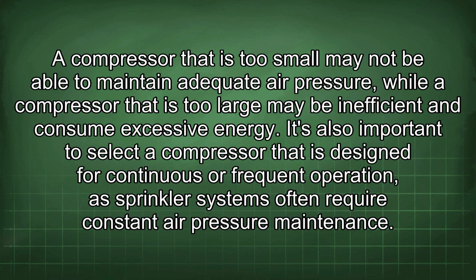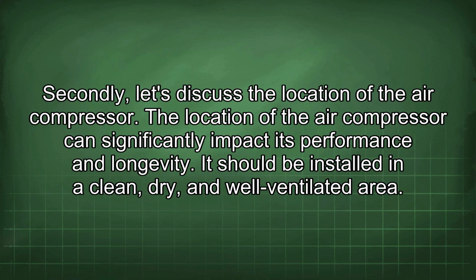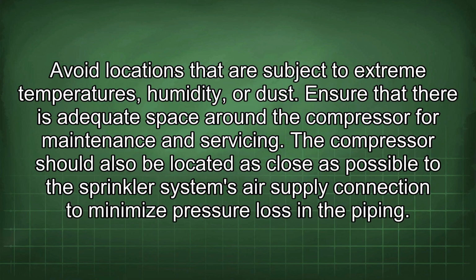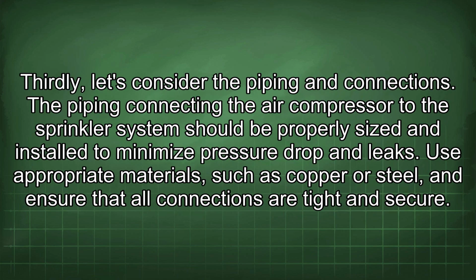It's also important to select a compressor that is designed for continuous or frequent operation, as sprinkler systems often require constant air pressure maintenance. Secondly, let's discuss the location of the air compressor. The location of the air compressor can significantly impact its performance and longevity. It should be installed in a clean, dry, and well-ventilated area. Avoid locations that are subject to extreme temperatures, humidity, or dust. Ensure that there is adequate space around the compressor for maintenance and servicing. The compressor should also be located as close as possible to the sprinkler system's air supply connection to minimize pressure loss in the piping.